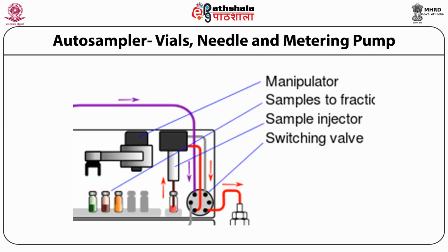All the operations like penetration, injection and rotation etc. are controlled by timers enabled in the autosampler. In order to avoid plugging of the needle and ensure a reproducibility of sample volume for every injection, the samples should be filtered and made absolutely free from any particulate matter.